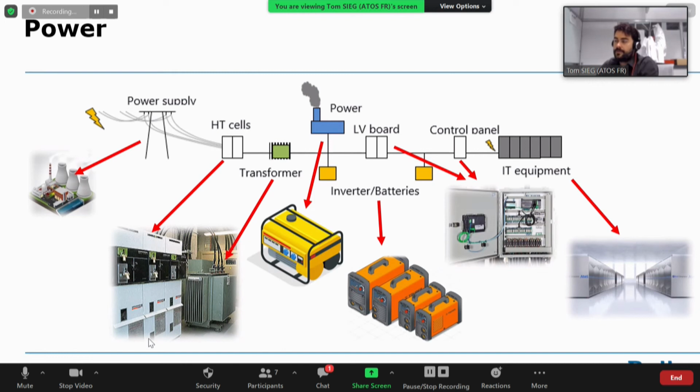If your business just needs a little more compute, a little more calculation capacity, you will be able to add compute into your cluster because you take into account 30% of space inside your cluster. You take into account a couple of electricity margin, so you will not have to change the electricity infrastructure. You just have to put servers in place. You have the place, the electricity, and the cooling capacity. So the 30% is there for the short-term evolving, I mean the 5 years evolving.